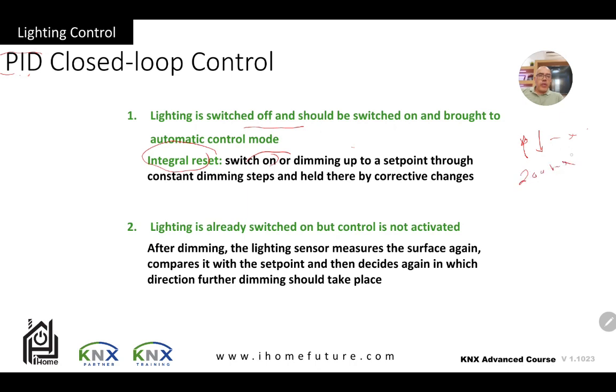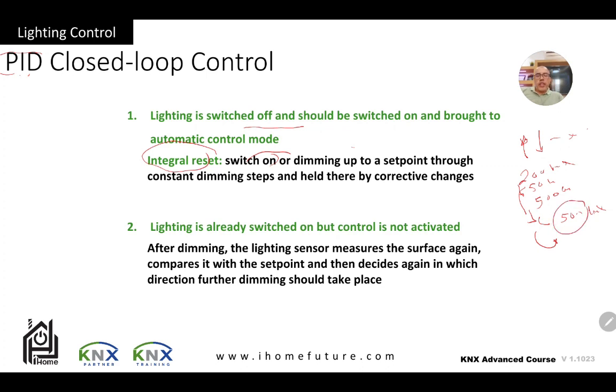For example, when I turn the light on it might be at 200 lux, and I want to reach 500 lux, so I increase by steps — say 50 lux at a time — keep increasing until I reach 500 lux. If changes happen, like the sun going down and external light decreasing, I detect the variable change and increase the artificial light slightly to always maintain 500 lux. If the light is already on but control is not yet active, once activated, the dimming oscillates up and down to reach the desired brightness. This is closed loop control for constant lighting.